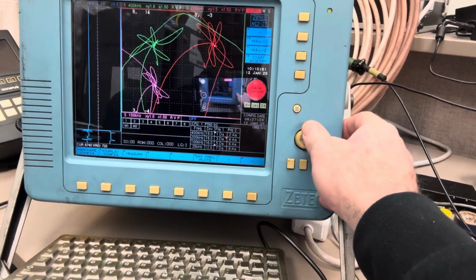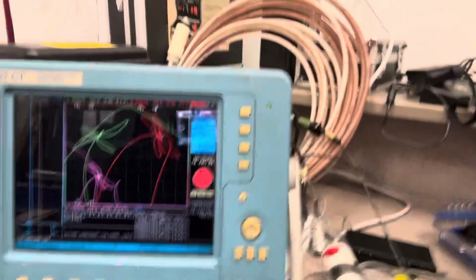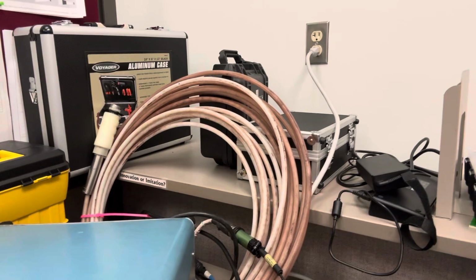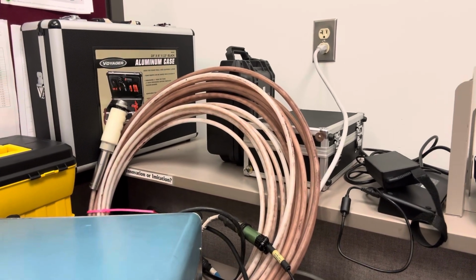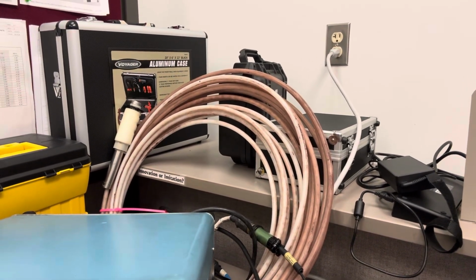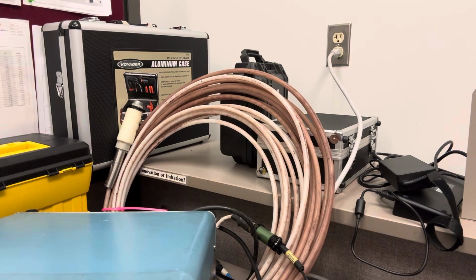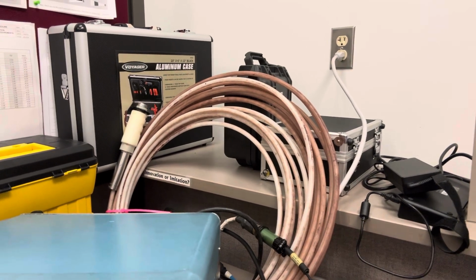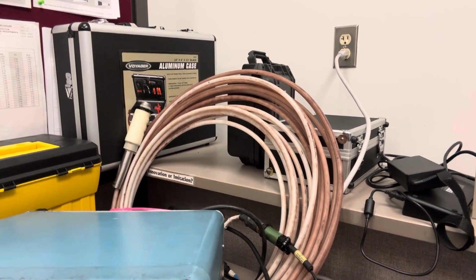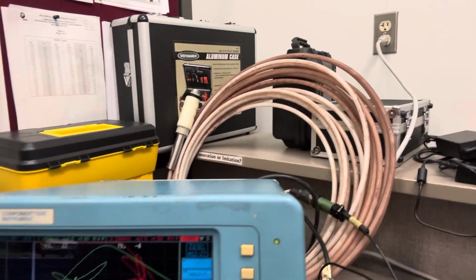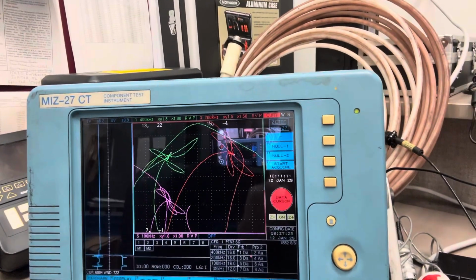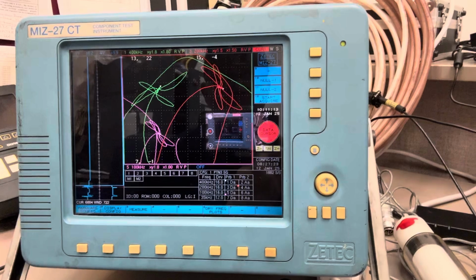When you go inspect actual tubing, that's an actual probe, kind of all spooled up right now, but it's 110 feet long. It gets inserted into a tube by robot, and once it goes all the way through, it's retracted at about 40 to 100 inches a second, and you're recording the data on the pullback.